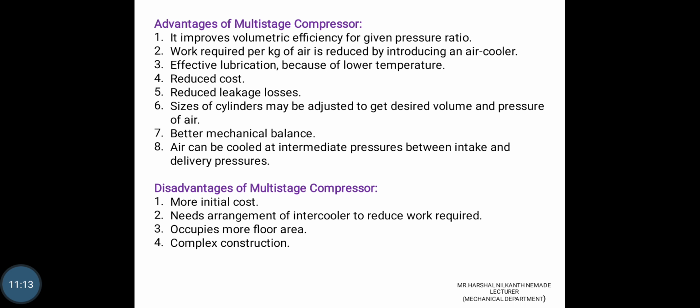Advantages of a multi-stage air compressor: it improves the volumetric efficiency for the given pressure ratio. The work required per kg of air is reduced by introducing the air cooler. Effective lubrication because of the lower temperature. Reduced cost and reduced leakage losses. The size of the cylinder may be adjusted to get the desired volume and pressure of the air. Better mechanical balance. Air can be cooled at intermediate pressure between the intake and delivery pressure.